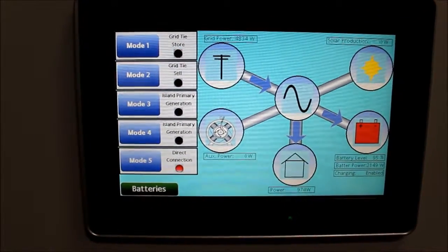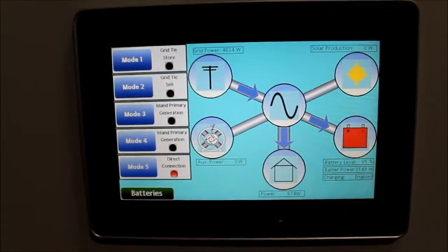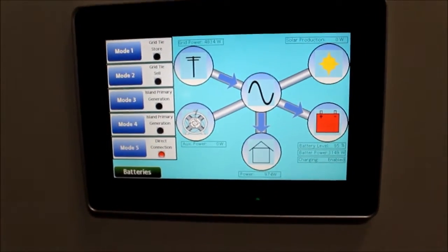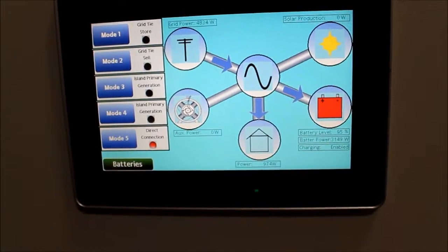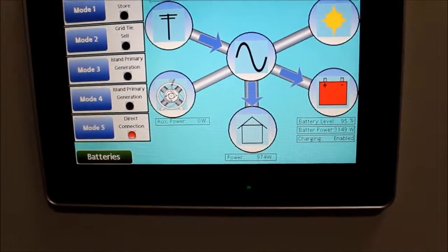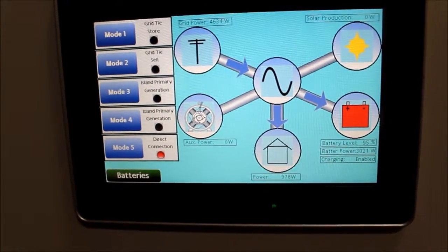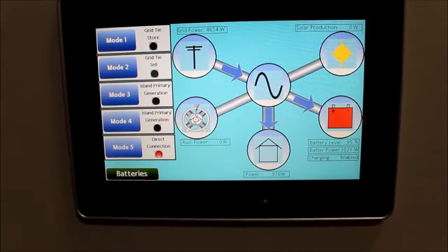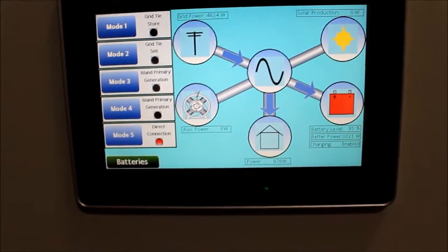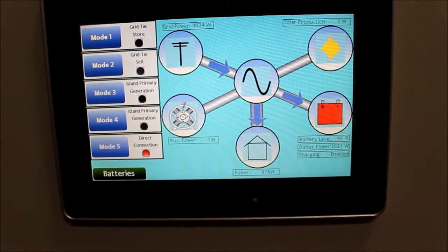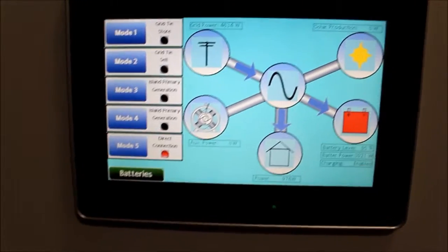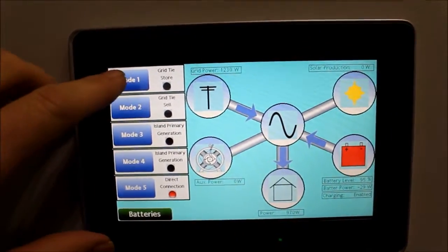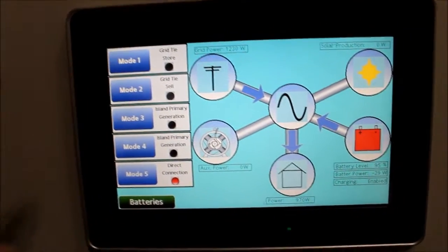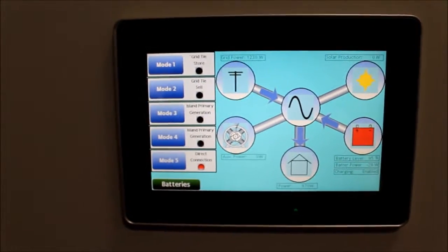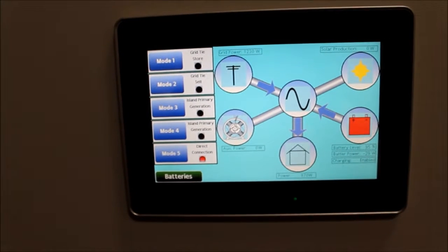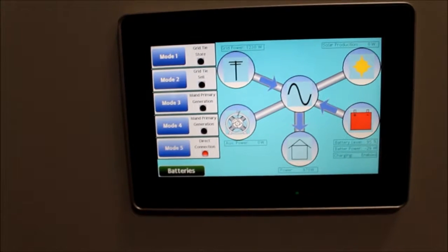The large clunk sound that you heard was the transfer switch changing over, and you will now see that the load is being directly served by the grid. The batteries are still charging because they are still below their preset level. Okay. Now I'm going to put the system back into mode 1. In a few moments the HMI will update, showing that the system has indeed returned to mode 1.